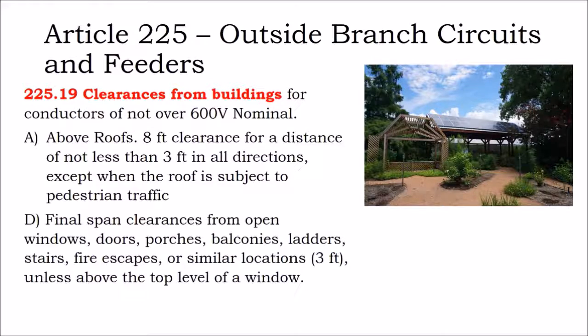Clearances from buildings for conductors not over 600 volts, above rooftops: 8 feet above the roof, or not less than 3 feet away from the roof in all directions, except when the roof is subject to pedestrian traffic. So if there's a rooftop deck and you have an overhead power line going across your rooftop deck, that may need to be 18 feet high instead of 8 feet high.